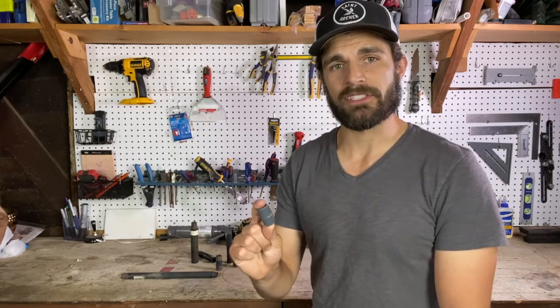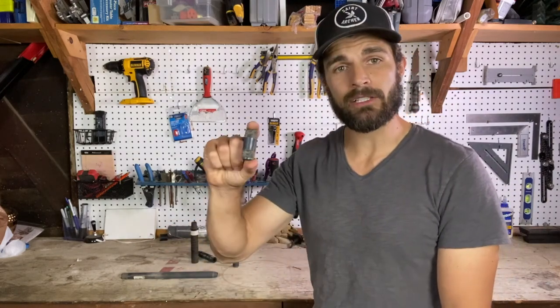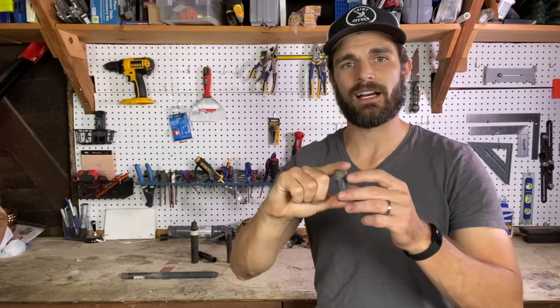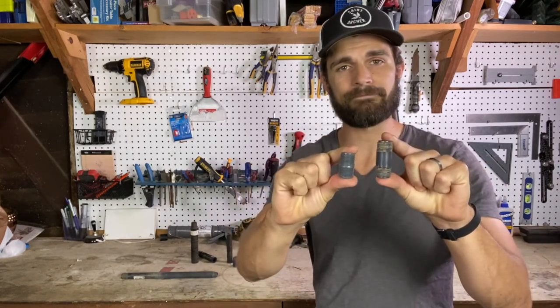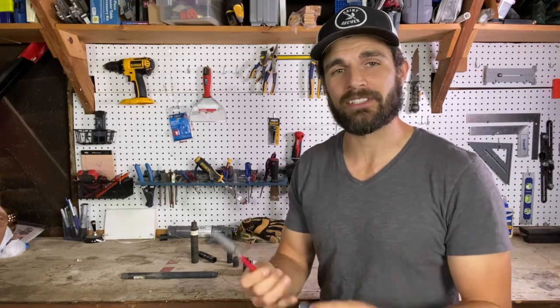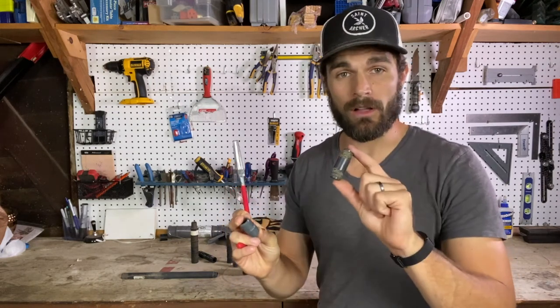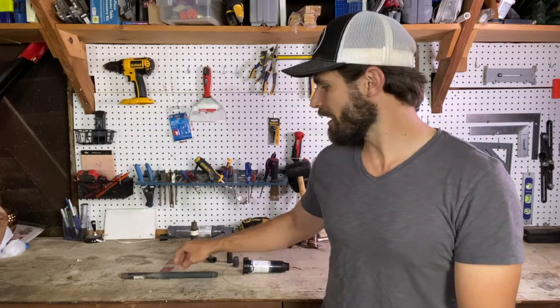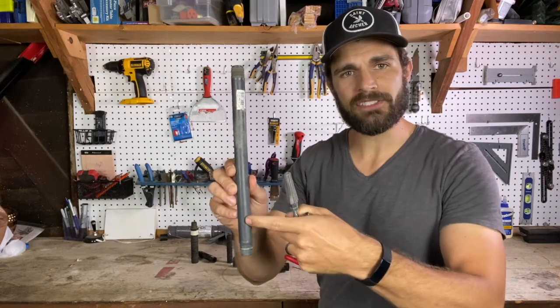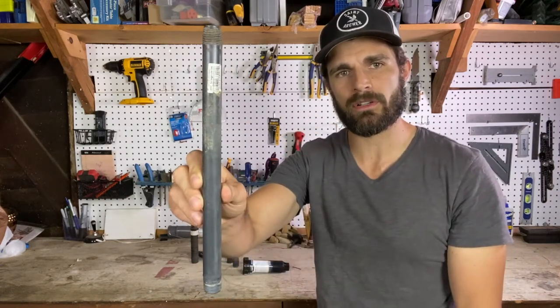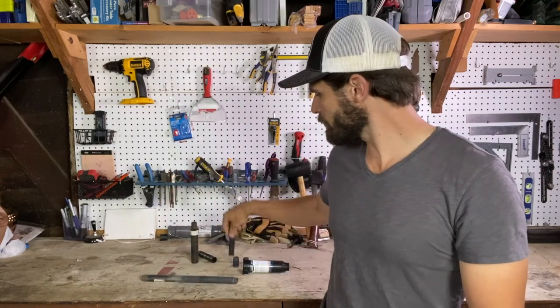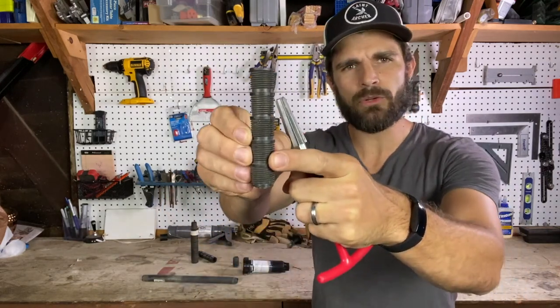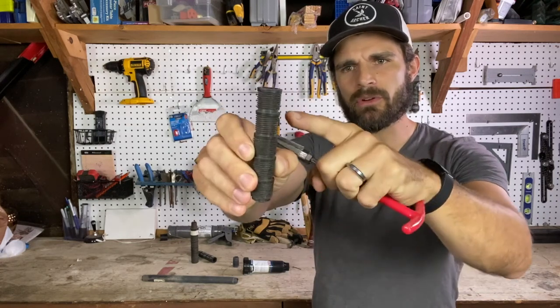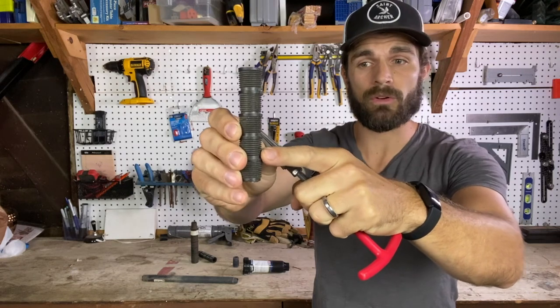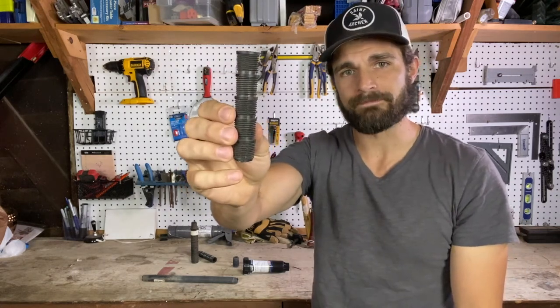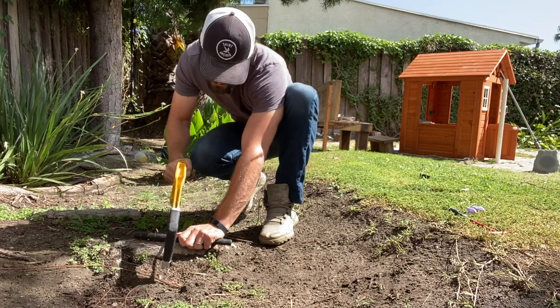So all you're going to do to fix that is to take a higher riser than what you previously had attached to the sprinkler head and add height. It's the same concept of taking the extractor and pulling out the riser and either adding a taller or a shorter variation. Now, there are a couple different kinds. There are the ones that are fixed. So as you can see, you can't cut this shorter or taller depending on your needs, but they also make ones where they have individual lines drawn on there. So what you can do is cut these off based on your needs or the height that you need for the riser. I use a hacksaw for that, or just a straight edge, whatever works for you.